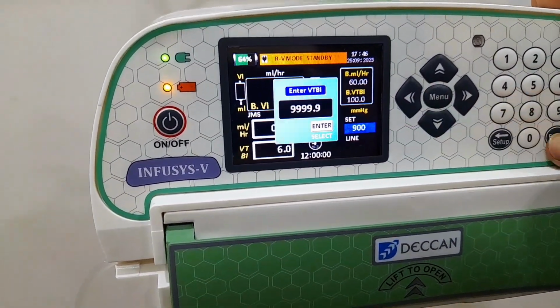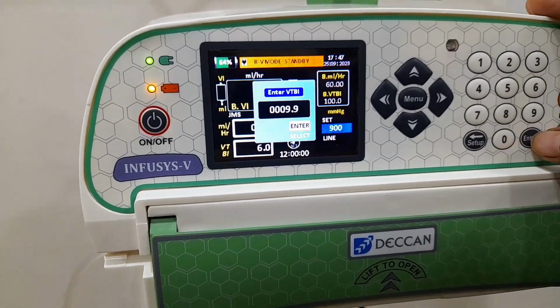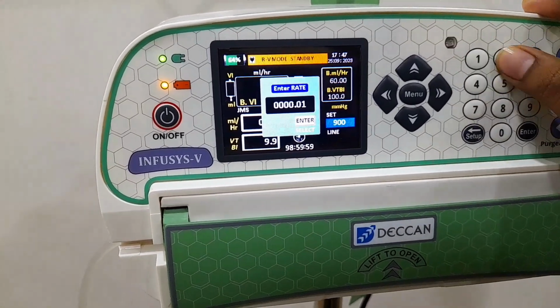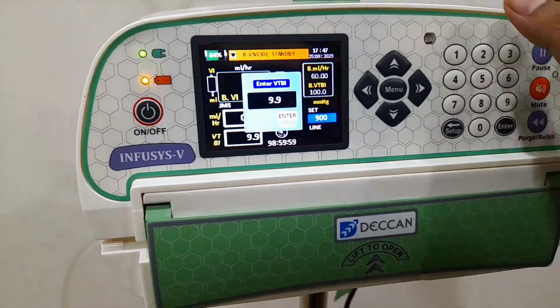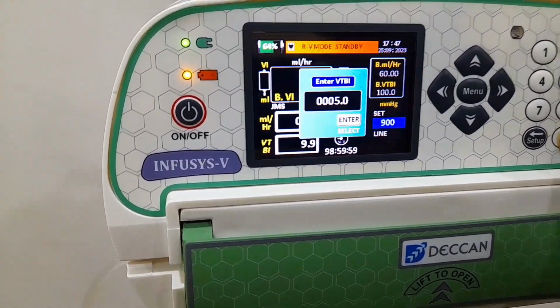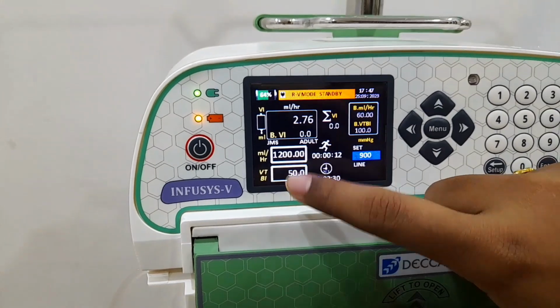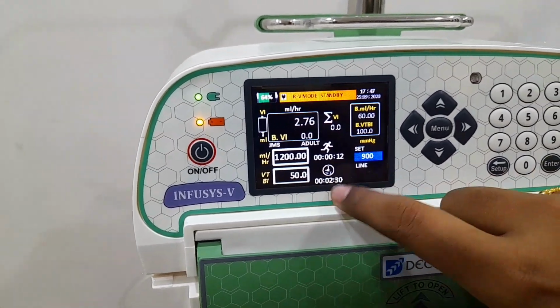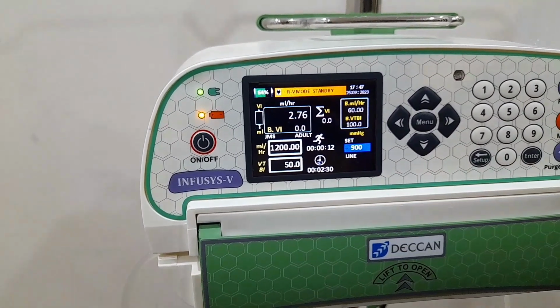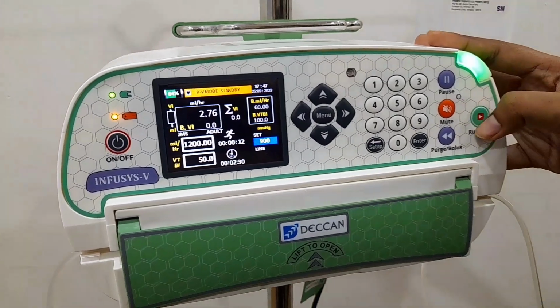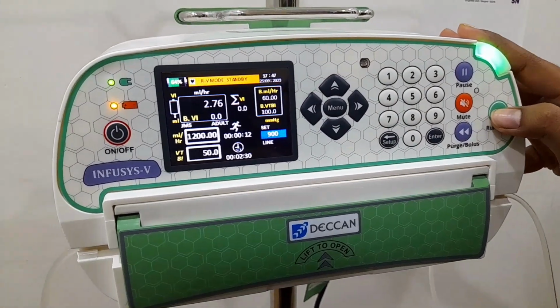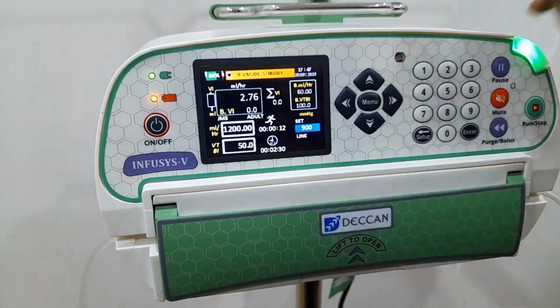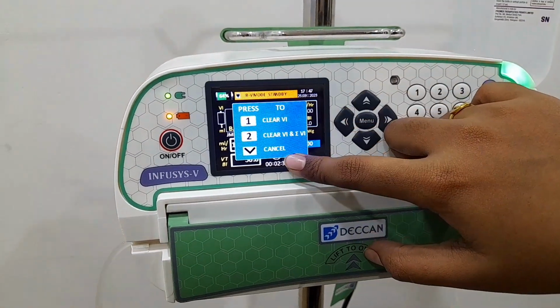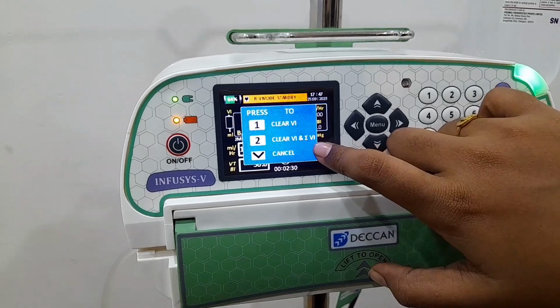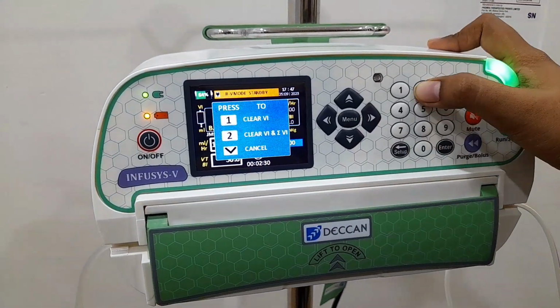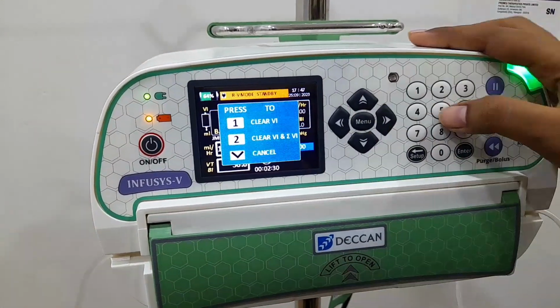We can set up to 9999.9. Here we are going to set rate as 1200 ml per hour and VTBI as 50 ml. Once we set, we can see the set rate and set volume here. Based on this, the calculated time will appear. Now we can press the run or stop key to start infusion. Once we start the infusion, the VI will appear here. Here we are going to choose the option to start a new infusion.